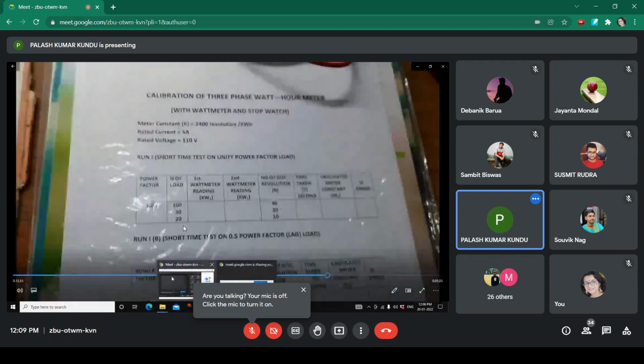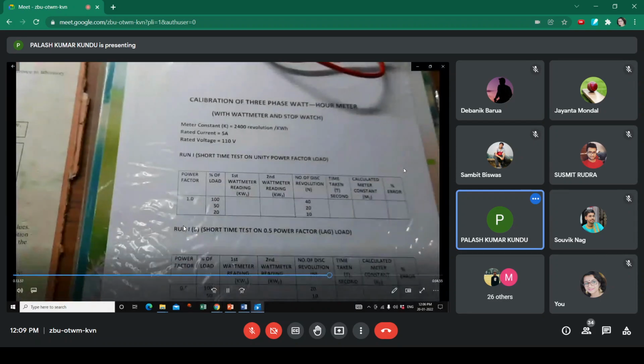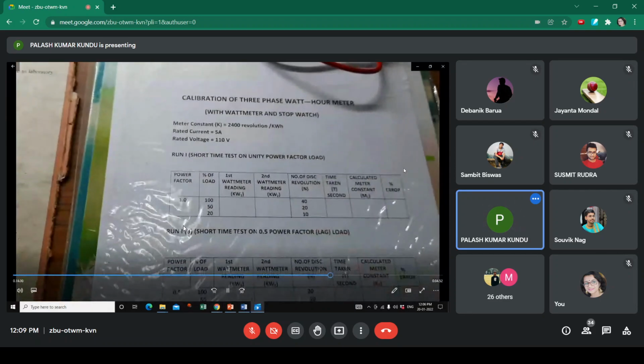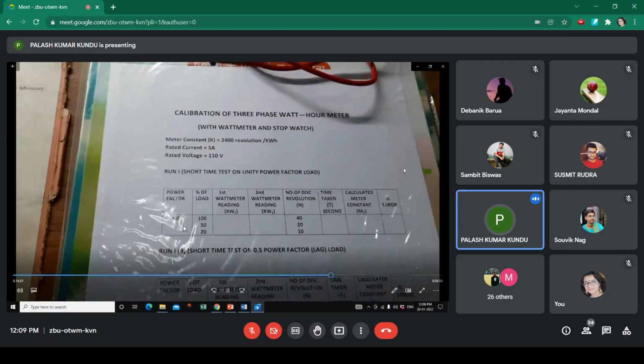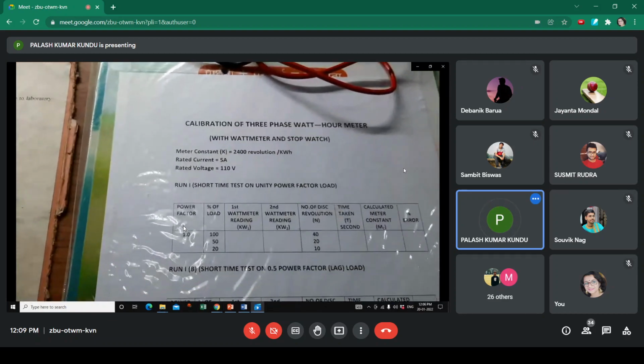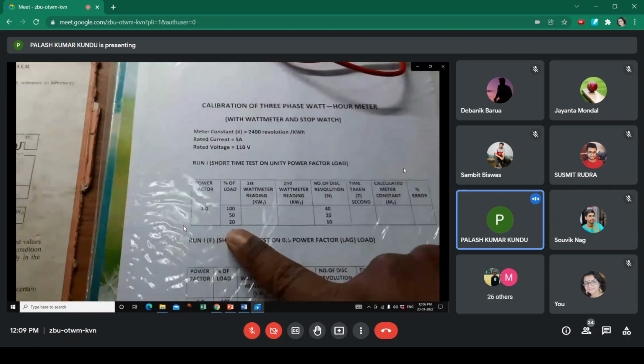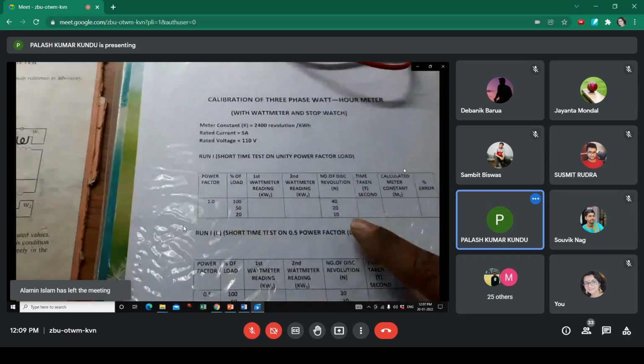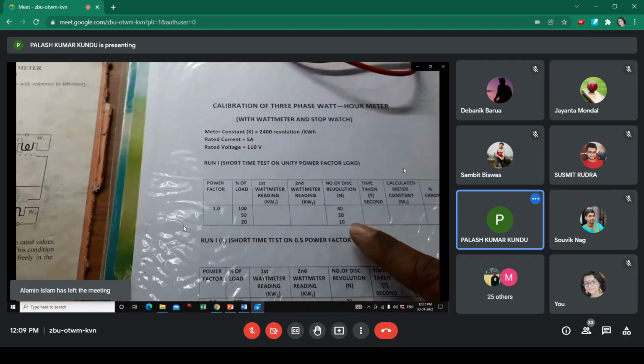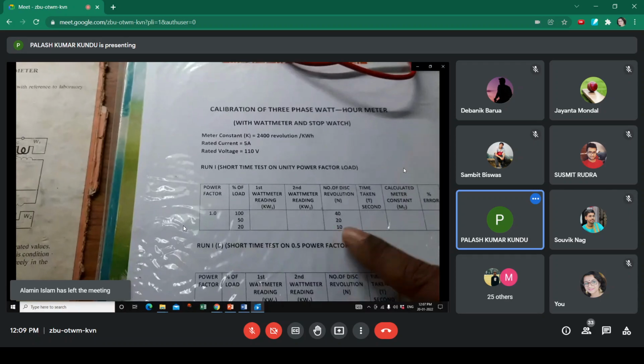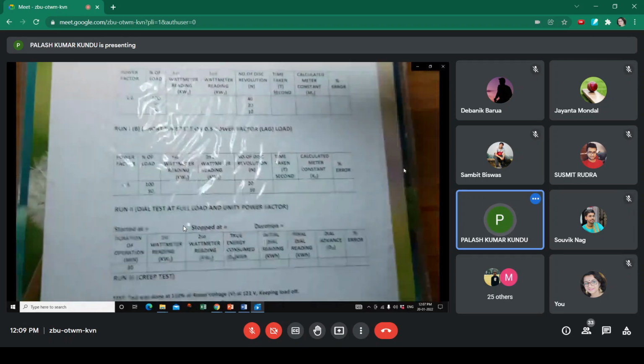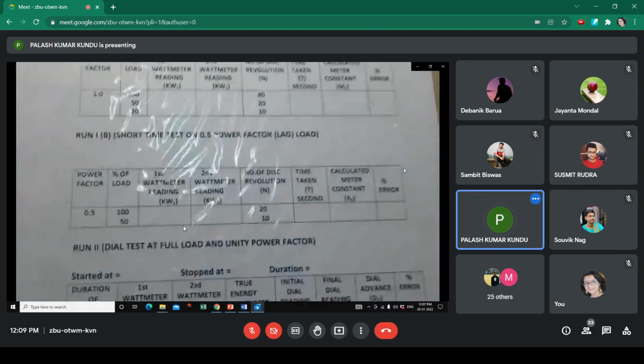Now for 50% load, the same procedure has to be done, but for 20 revolutions. For 20% load, you have to take the reading for 10 revolutions. More or less the same procedure applies for run 1B also.